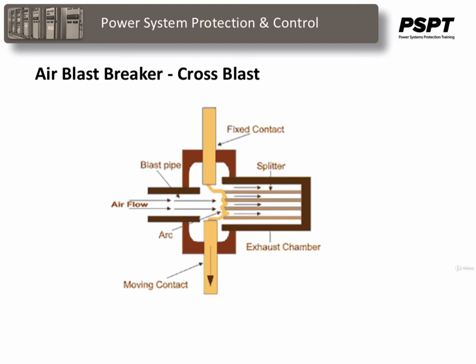The working principle of cross-blast air circuit breakers is quite simple. In this system, the blast pipe is fixed perpendicular to the moving contact in the arcing chamber, and on the opposite side of the arcing chamber, which is also fitted with an exhaust chamber, so that the air coming from the blast pipe can enter into the exhaust chamber through the contact gap of the breaker. The exhaust chamber is fitted with arc splitters.